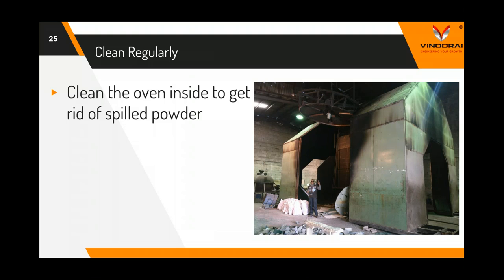Cleaning the spilled powder inside the oven is very, very important, because all of us know that LLDPE powder is a byproduct of petroleum and is also petroleum in itself. It is flammable, and too much deposition of powder inside your oven can cause you safety issues in case of fire. Also, one more thing is the spilled powder inside your oven is taking in the heat every time in every cycle, and it costs you a little bit of fuel in every cycle, hence increasing your fuel consumption.